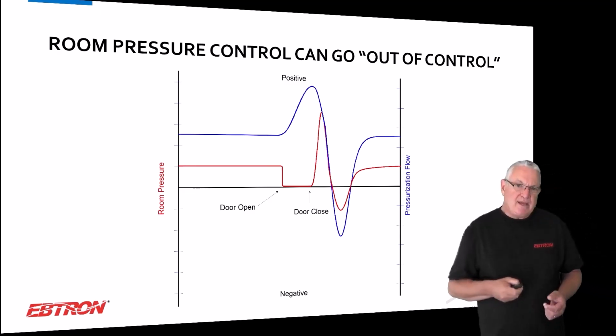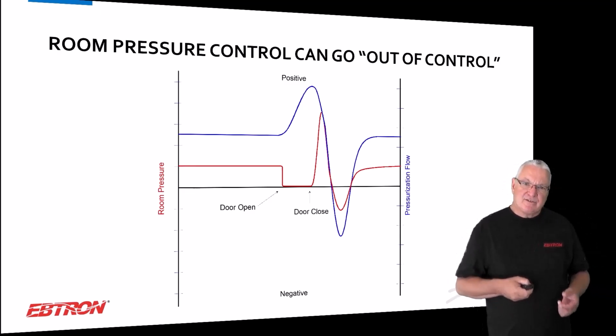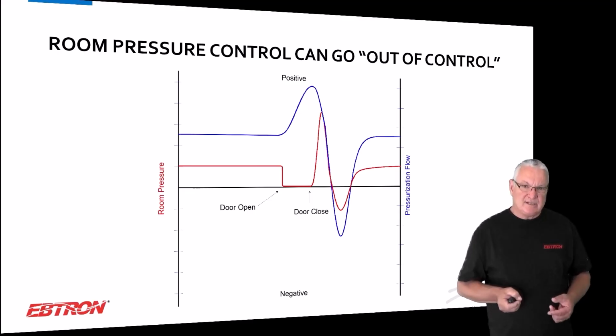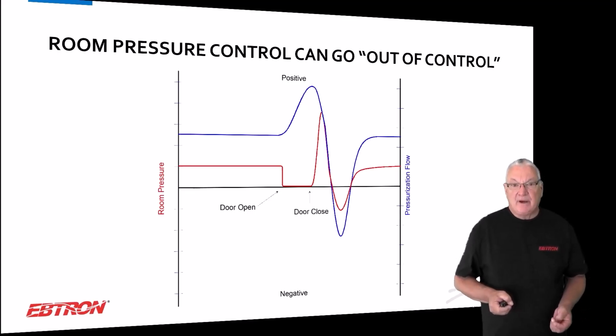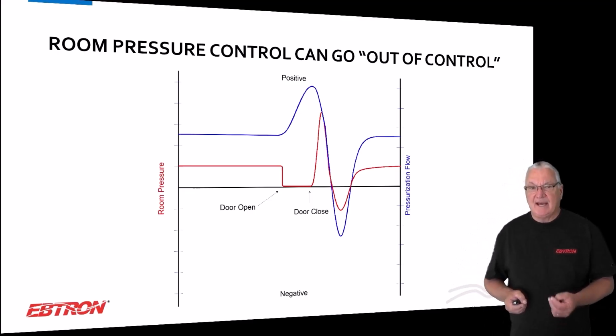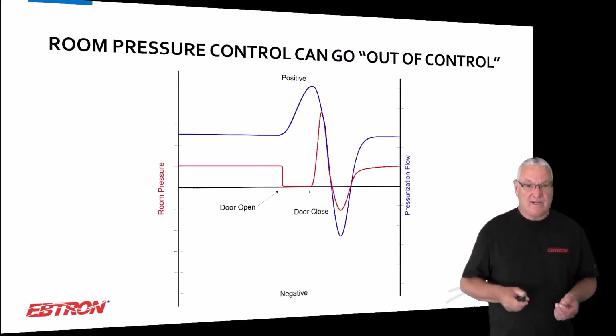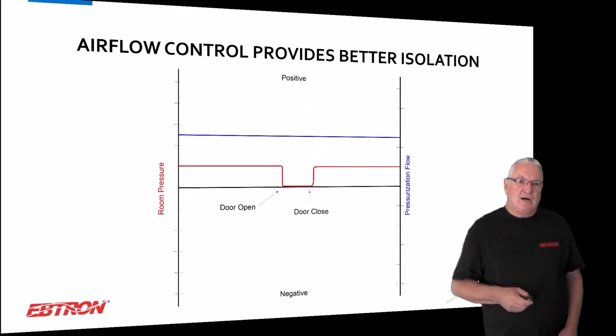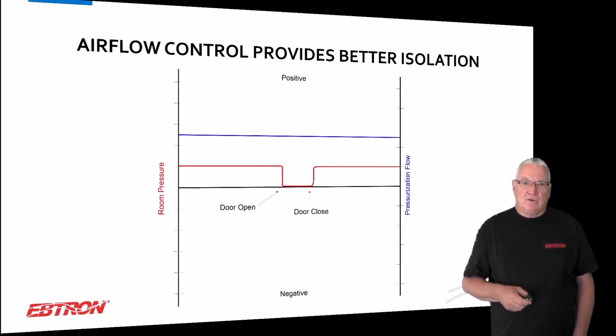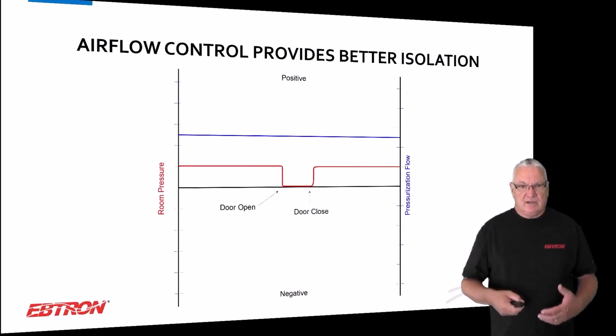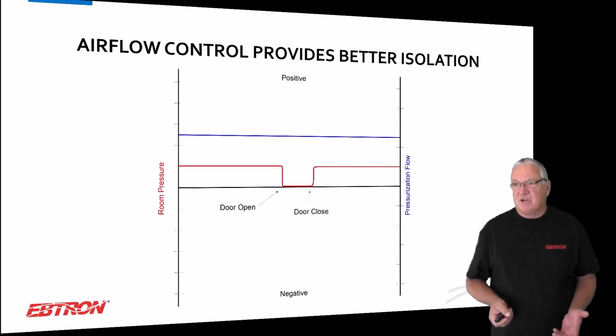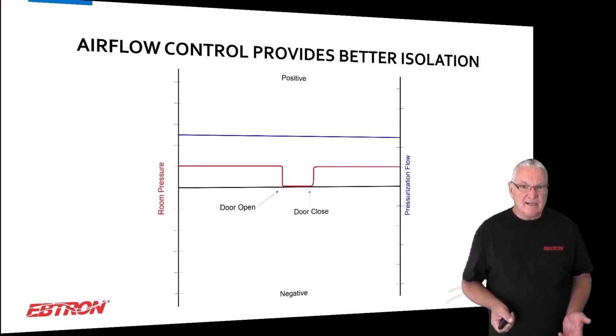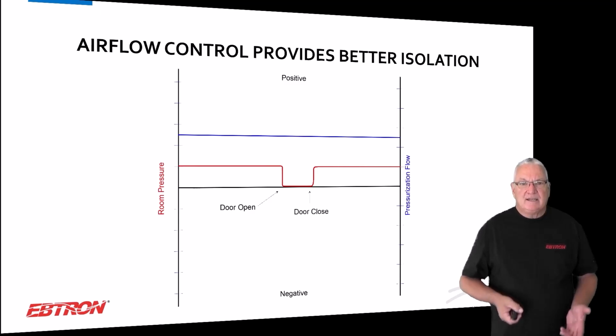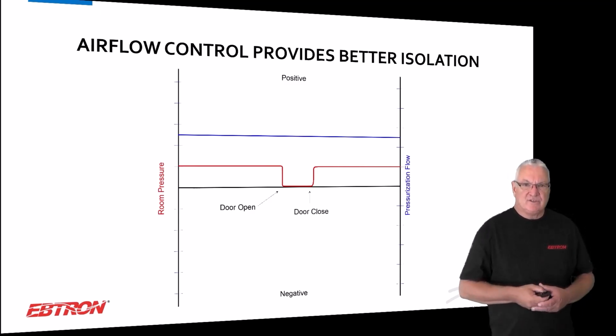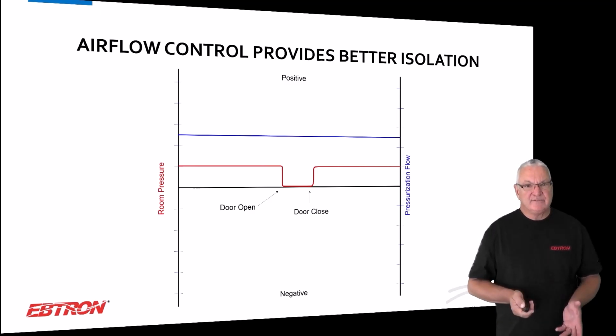Now, you may or may not see that, depending on how fast you're sampling these pressure sensors. Or if you're integrating it, you might say, well, I don't see that, but it could be happening, and that is something that you really do not ever want to have happen. When you do airflow control, sure, you open the door and again, the pressure drops to nothing. You're not going to pressurize that space, okay? But the pressurization flow stays where you want it to be, meaning it's still positive, okay?